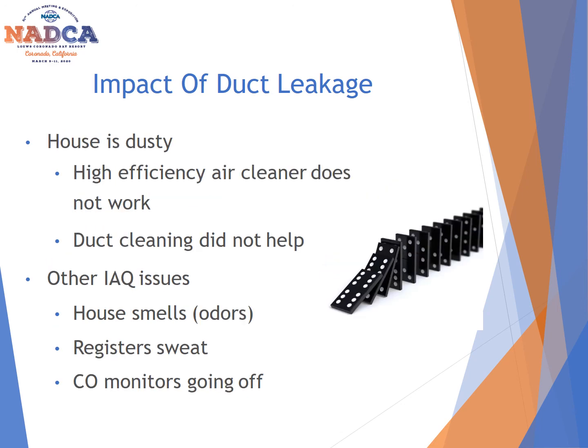The other issue that you run into when you have leaking ducts is not only is it blowing excessive air into attics and crawl spaces and areas you don't want it to, it can also suck air from spaces that you don't want it to be sucking from, including attics and crawl spaces. So you're pulling more dust and debris into the system, and therefore your ducts are getting dirty. The other thing that contributes is other indoor air quality issues, which include odors within the facility or within the home. Registers are starting to sweat because you're pulling more humid air into the area, and those registers are creating condensation, which then leads to microbial issues. You can also have CO monitors going off at the same time.